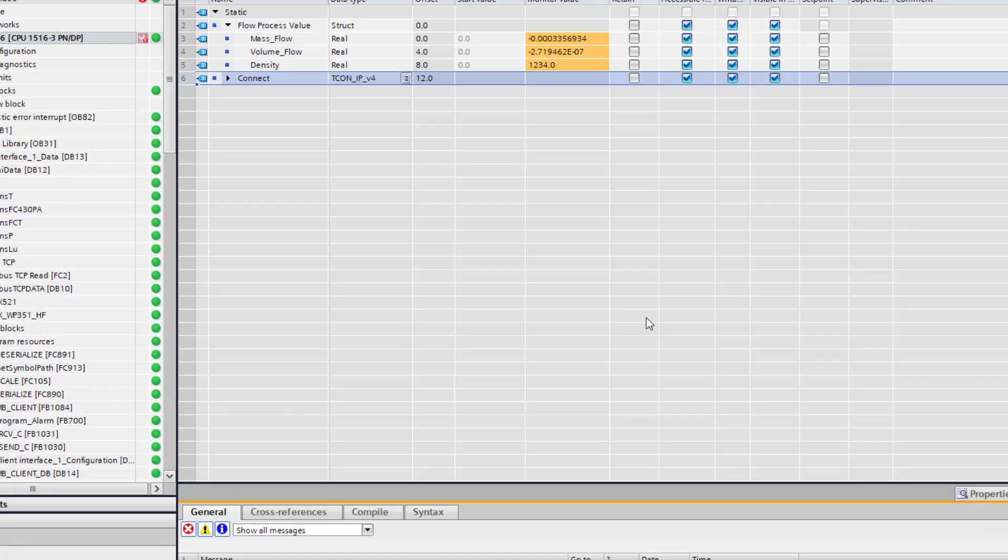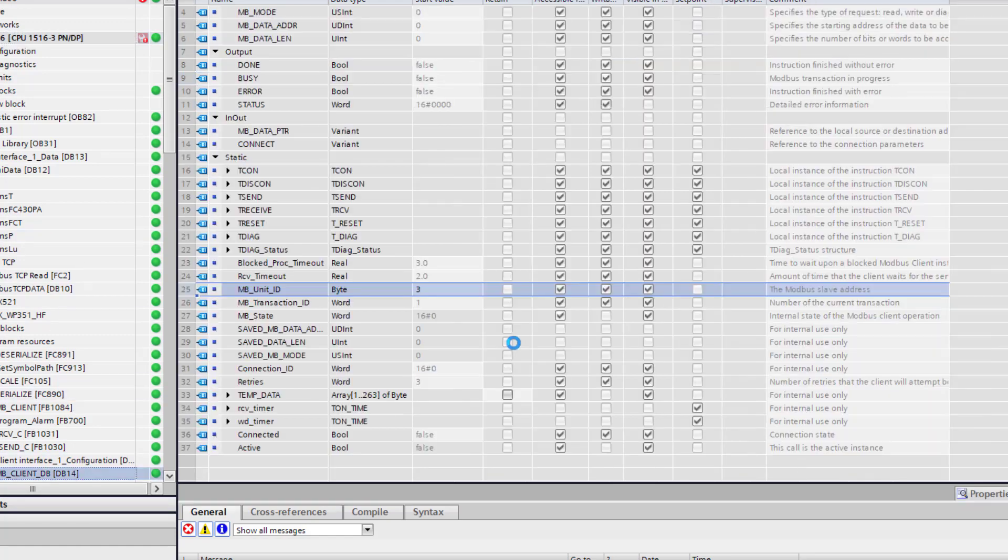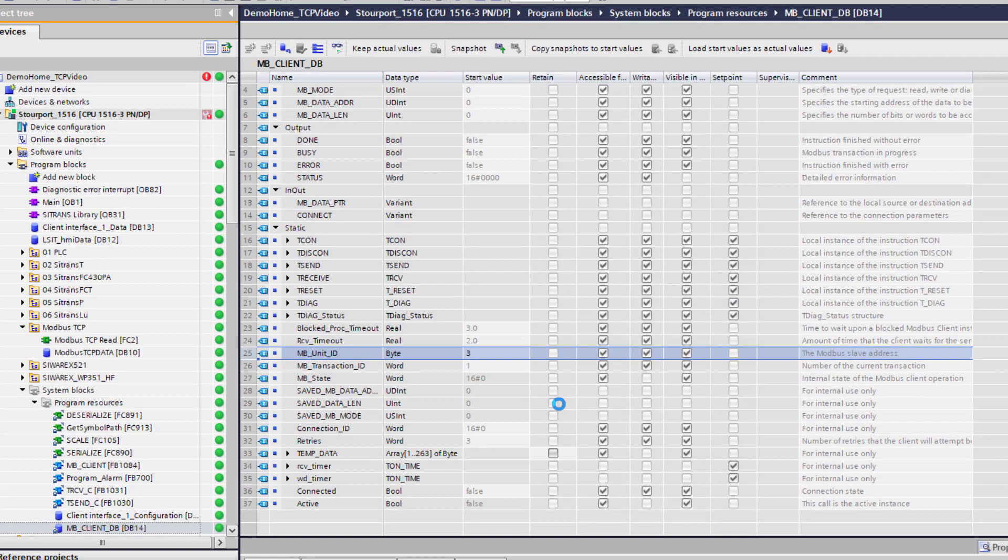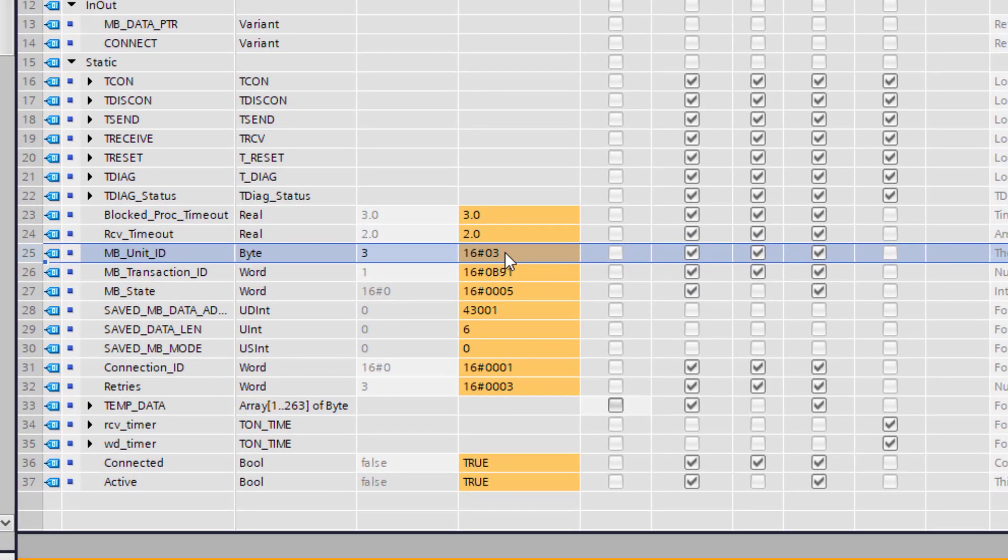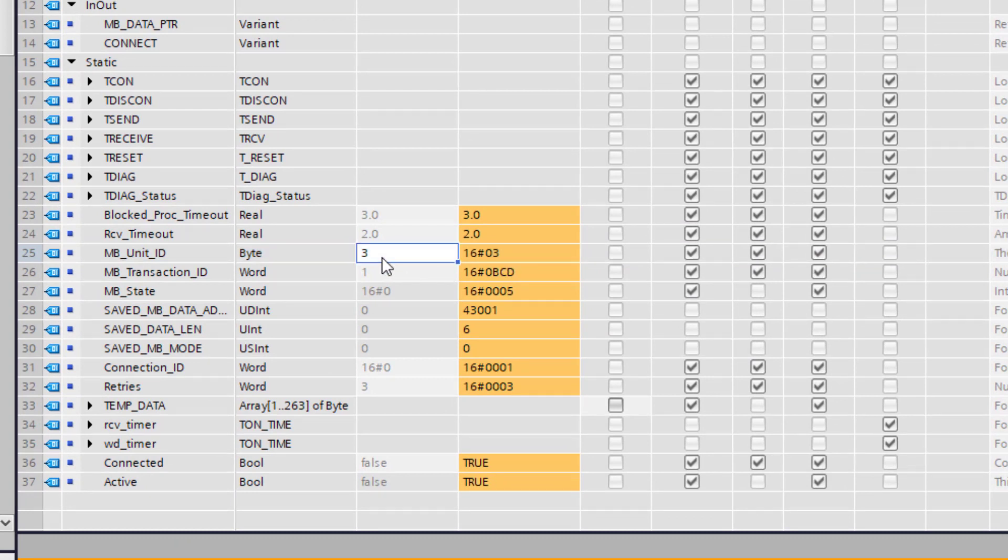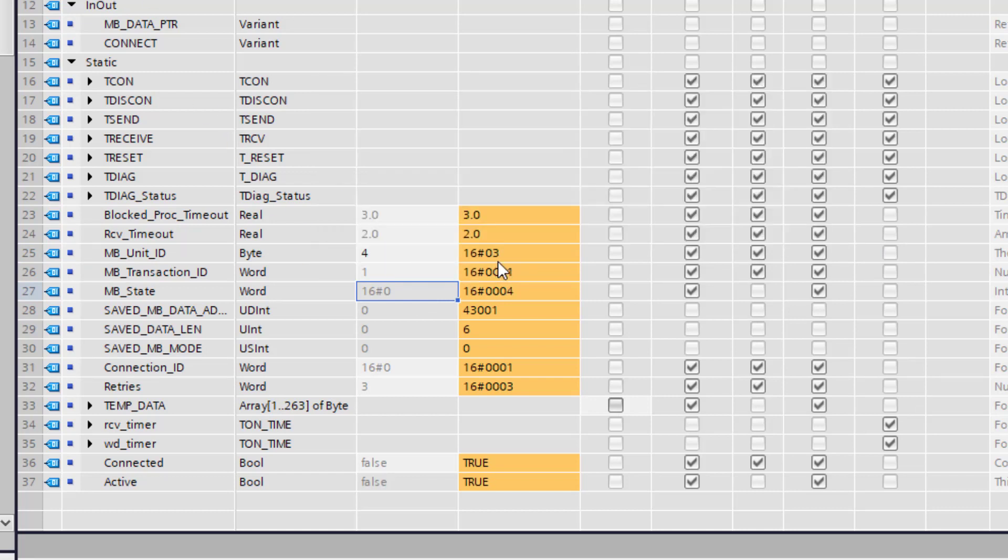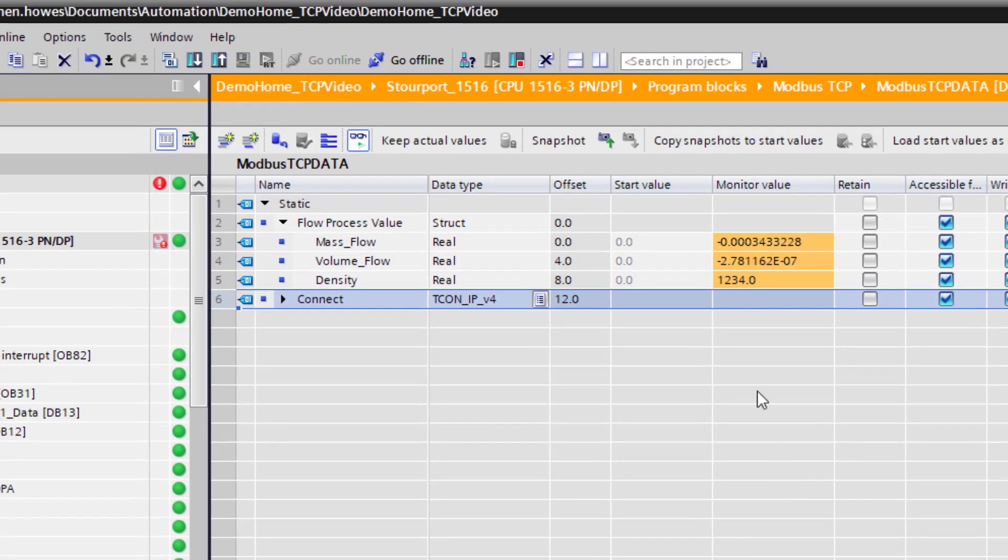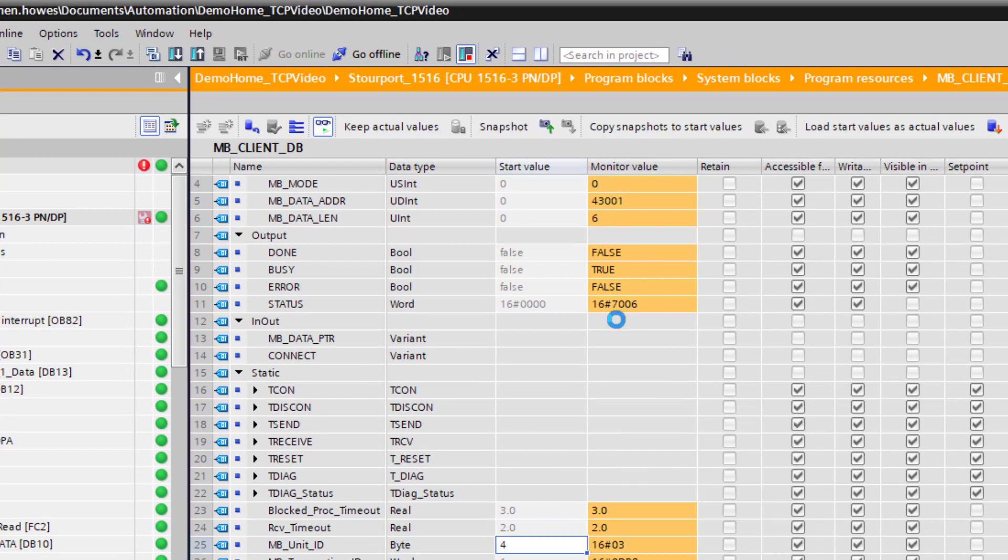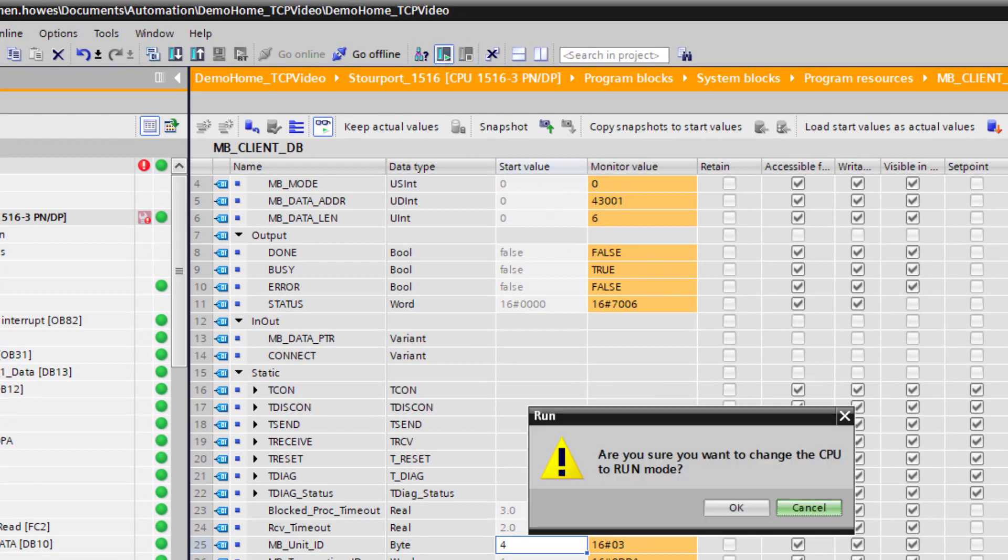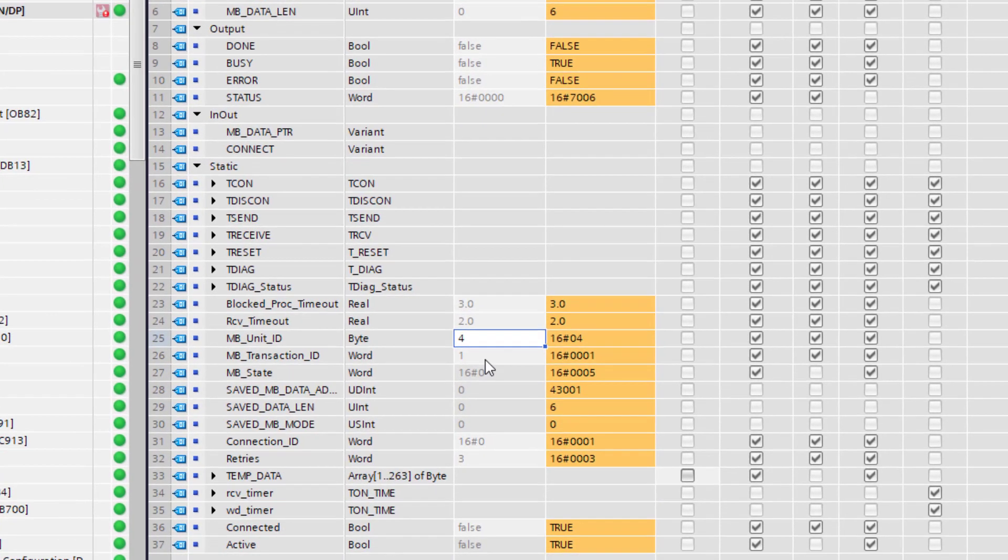I just wanted to show you one last tip just before we finished off because this may catch you out and it is to do with the MB client and the way the data moves within the data block. So you can see here there is my value and that is what it is reading back. So if I change that to four it is going to break everything. Download that. You can see here my initial value of three is still there. And if I go to my data block it is still happily reading the information. Now this can catch you out. What you need to do is just start and stop the PLC. And what you will see, it will reinitialize that block and it pushes the four back in.